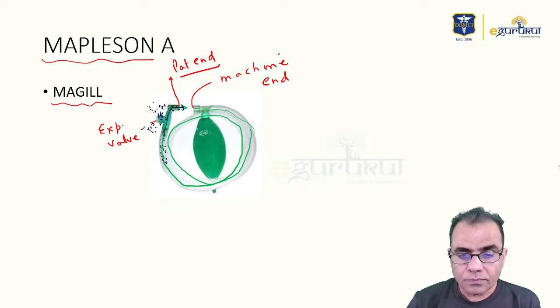So simply you can remember that the fresh gas flow recommendations, which we are going to discuss here, are meant to prevent rebreathing, and how they are calculated is of course much beyond your scope. They have done years and years of study to find the most appropriate fresh gas flow for each kind of circuit, which involves a lot of physics. So the fresh gas flow requirement for the Magill circuit, if you are using it for spontaneous ventilation, should be kept equal to the minute volume of the patient.